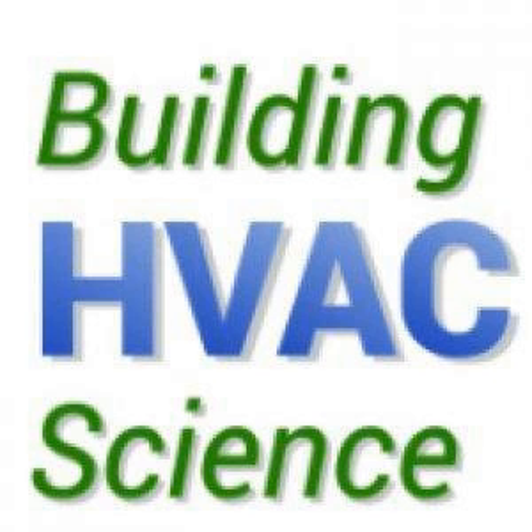Because we are from Canada, we are definitely a heating predominant sector. We have decided to put that heat in the fresh air stream to take advantage of that. So we don't have one heat source to recuperate, but 3 heat sources. Meaning that one of the standardized tests goes like this, Bill. When it is 32 Fahrenheit outdoor and 72 Fahrenheit indoor, and if you move 100 CFM, the fresh air exiting the unit before entering in the house or the apartment is at 102 Fahrenheit.